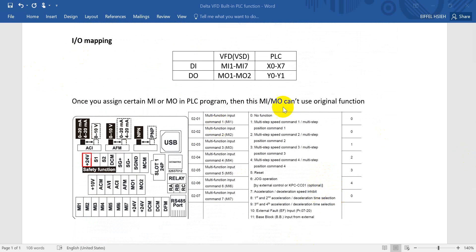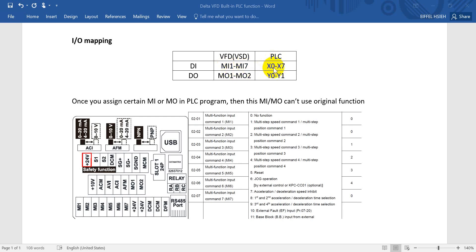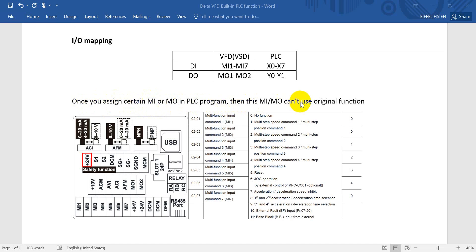Here we'll talk about the I/O mapping. So this is the default for the inverter. For MS300 we have seven inputs and two outputs. So the input we will call MI1 to MI7, but in PLC we'll define it as X0 to X7. And digital output in inverter is MO1, MO2, and in PLC will call Y0 and Y1. Here is an important concept: once you define you use this MI or MO in PLC program, then you cannot use the parameter to define this anymore unless you disable the PLC function.